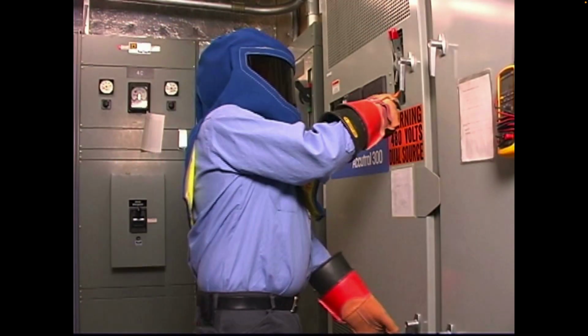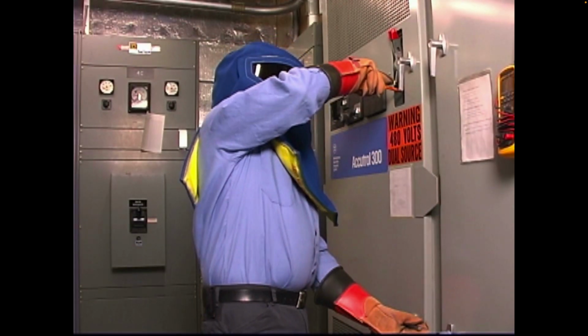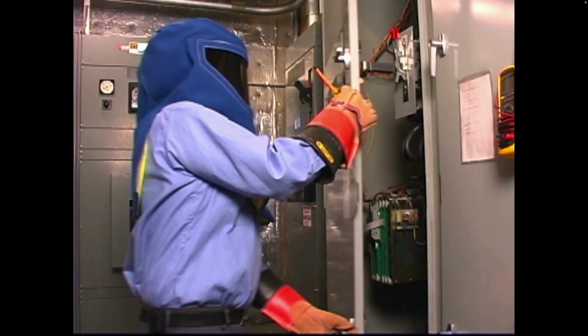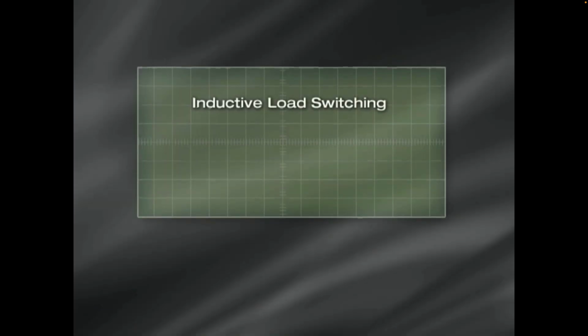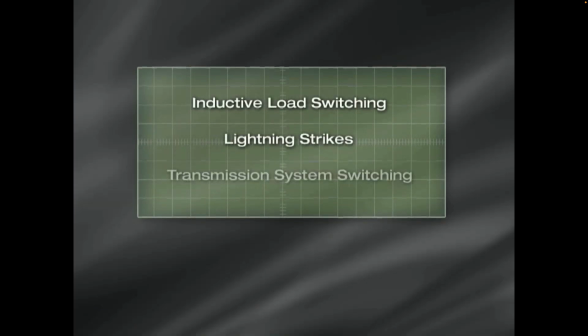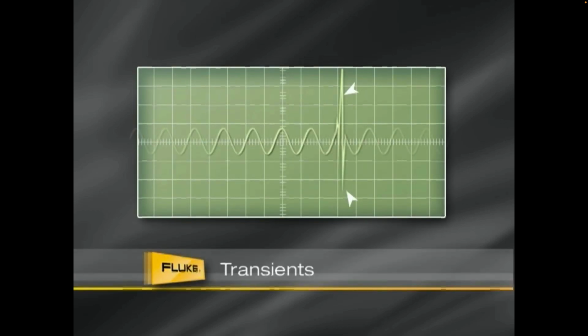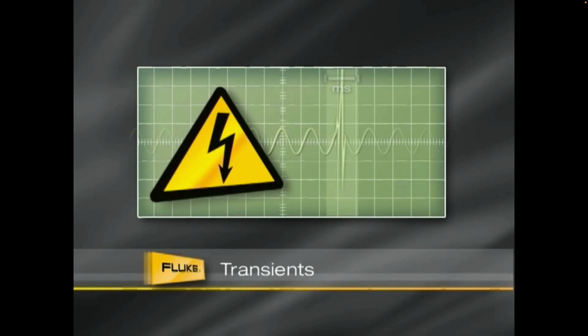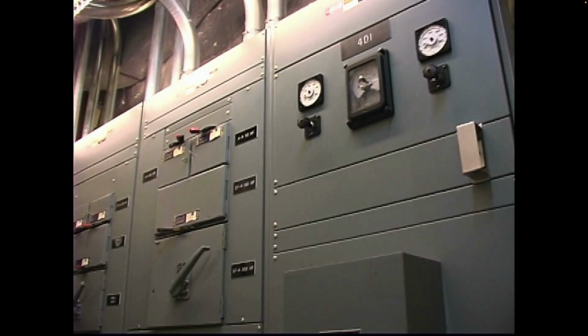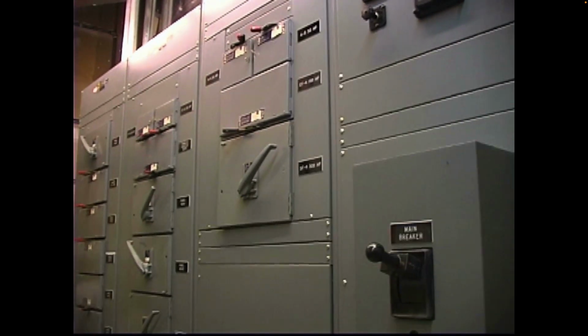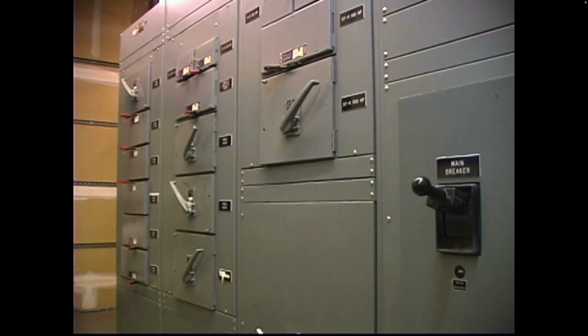Following these steps will help you work safely. But sometimes, even these steps can't prevent trouble. Switching of inductive loads, lightning strikes, and transmission system switching can generate huge voltage spikes. These voltage spikes, or transients, can last as long as 100 microseconds, but they can be extremely dangerous. In modern power systems, transients are present all the time, some small and some large.